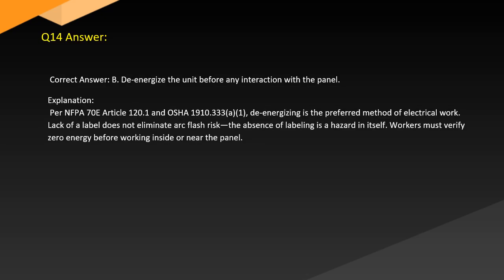Answer. Correct answer: B. De-energize the unit before any interaction with the panel. Explanation. Per NFPA 70E Article 120.1 and OSHA 1910.333(a)(1), de-energizing is the preferred method of electrical work. Lack of a label does not eliminate arc flash risk. The absence of labeling is a hazard in itself. Workers must verify zero energy before working inside or near the panel.